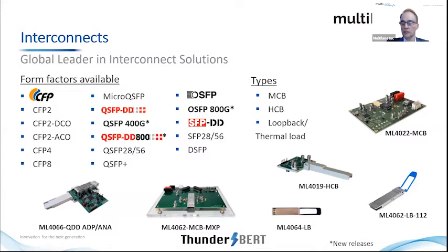We support module compliance boards to be able to test transceiver modules, and host compliance boards that you can plug into your host system or switch, so that you can have access to the high-speed I/O interface. We also have loopbacks and thermal loads for testing the thermal characteristics of your system, and also power loading your system as part of engineering or as part of an installation setup.